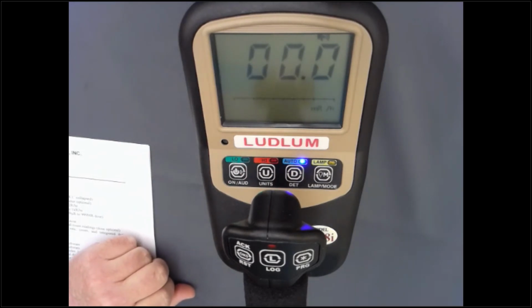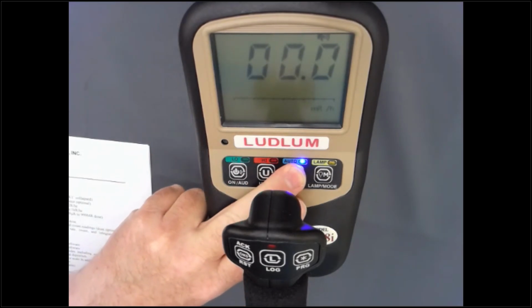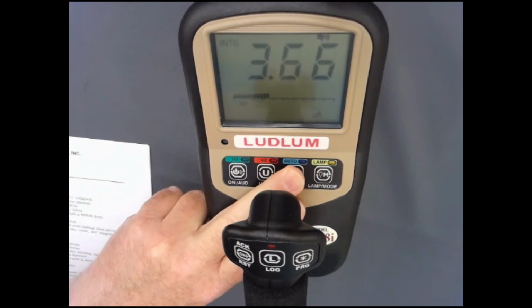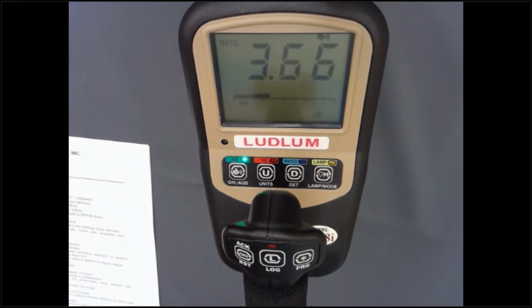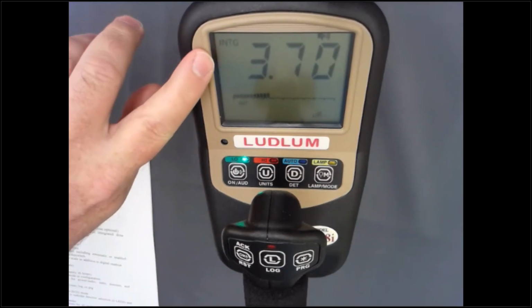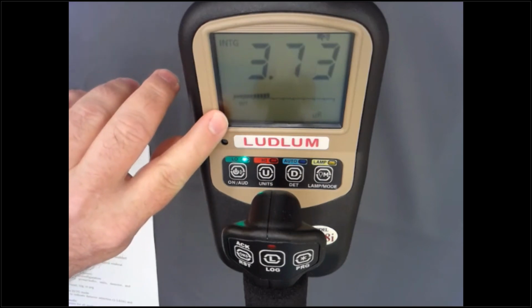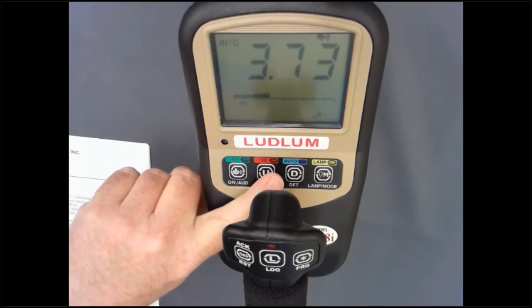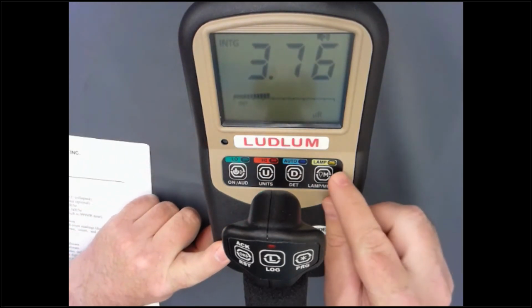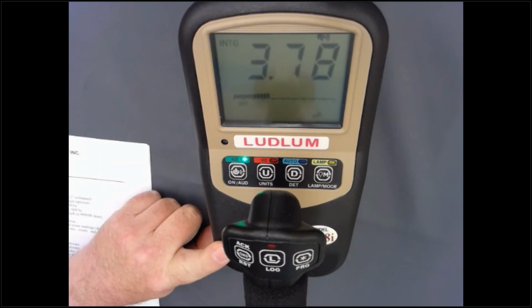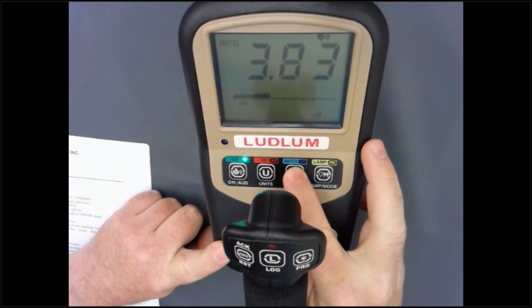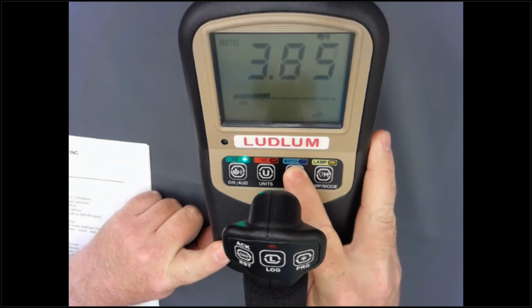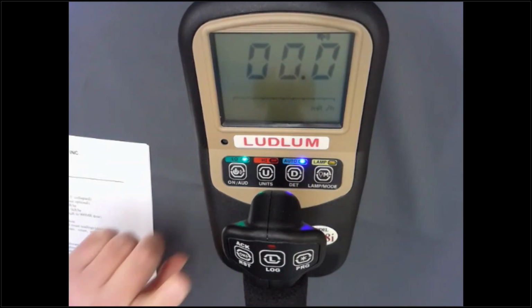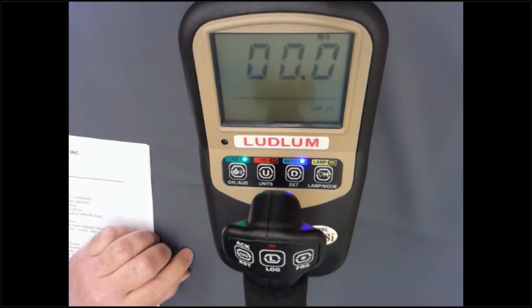To have direct access to the internal detector, we're going to press and hold the detector button for 3 beeps, approximately 2 seconds. And now we have switched to the internal detector, and we can see a fixed reading. In this case, we're looking at the integrated dose of the internal detector as indicated by the INT, and we can see a reading of 3.73 micro R. As with other instruments, you can actually switch back and forth through the modes, which I'll demonstrate here in a moment. To return back to the main detector, external detector, you press and hold the detector button for 3 beeps, approximately 2 seconds, and return to the external detector.